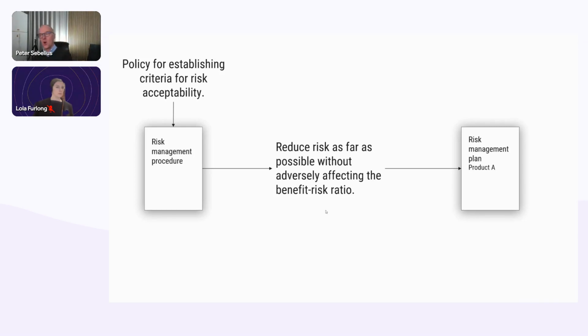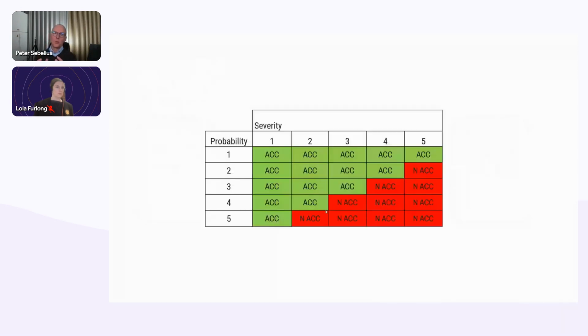So the consequence of this requirement here is that if you're planning to sell to the EU, you need to include this thinking or statement in your policy. And it should then be found in your risk management plan as well. Now, most companies would still do risk evaluation using a matrix like this, which looks at the magnitude of risk. But the MDR says you need to reduce it as far as possible, which is more of a relative measure.